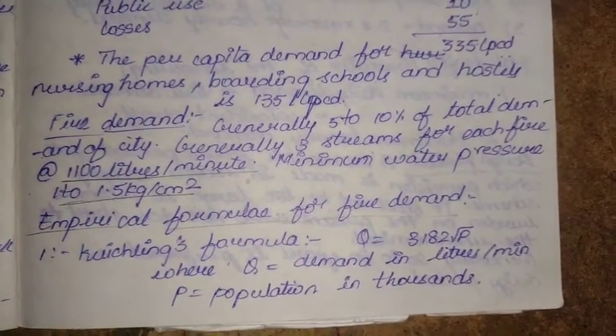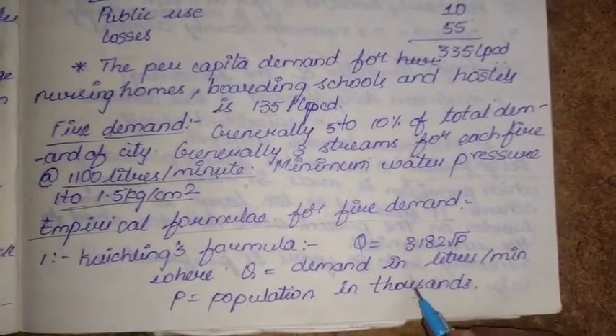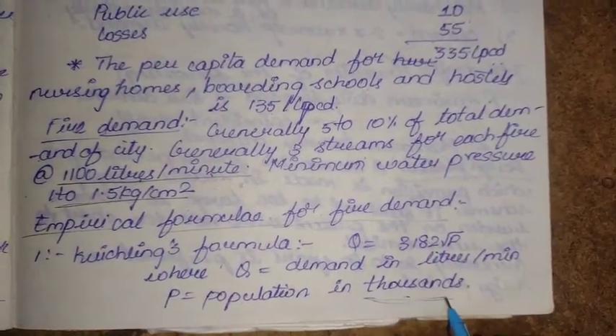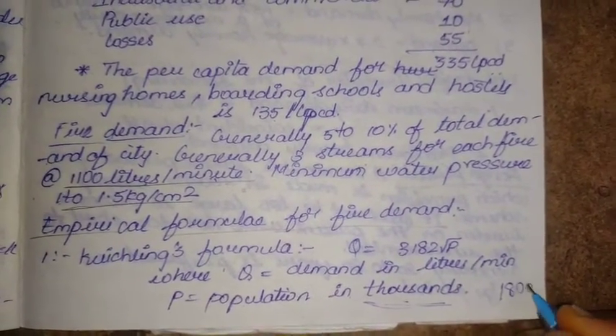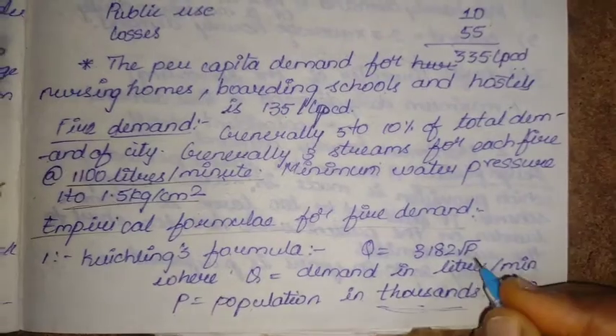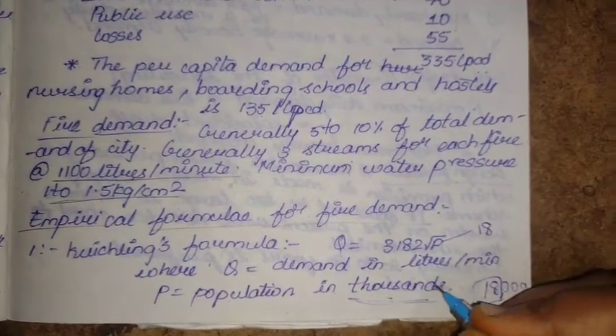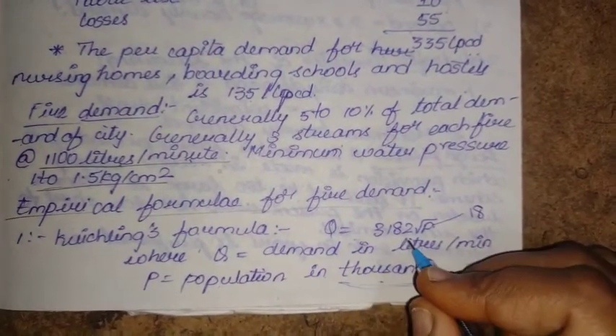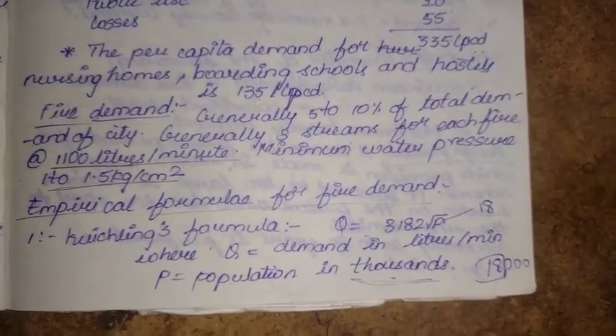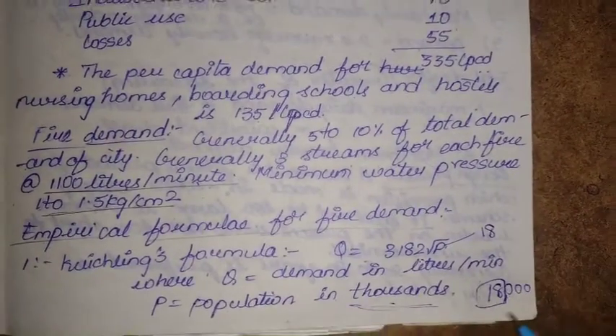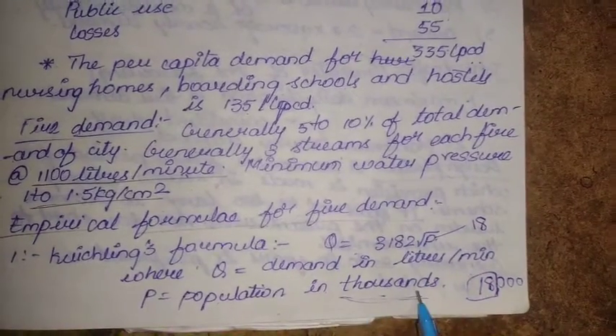In the Kuichling formula Q = 3182√P, P is the population in thousands. For example, if the population is 18,000 we substitute P as 18. The value 3182 is a constant. When P is substituted in thousands, the result Q is obtained in liters per minute.